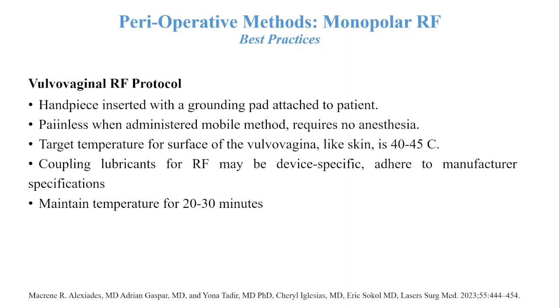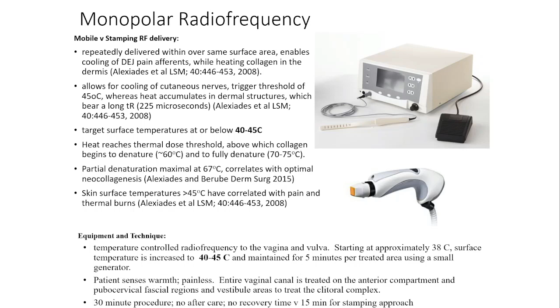This is just to show you a couple of versions of this type of probe-based system, and the way the treatment is delivered, it's a constant movement of the handpiece. You can either do the entire vault or do quadrants. Get to target temperature, go to the next quadrant, and maintain. And that constant mobility, maintaining continual movement, is maintaining the target temperature of 40 to 45 for that 20-minute period. And it has a timer on the device so you know that you've delivered adequate energies.